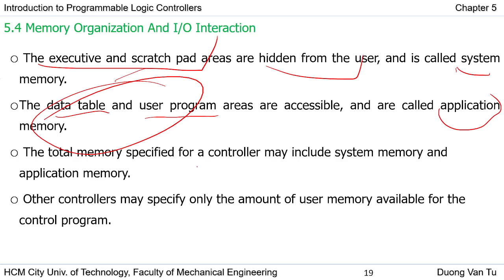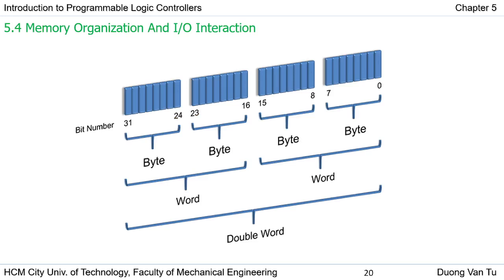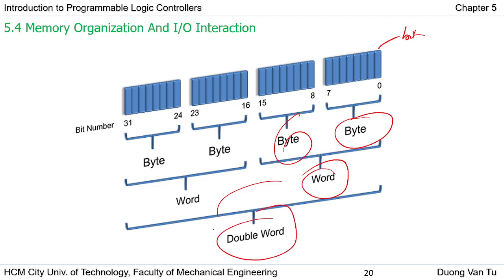The total memory specified for a PLC may include both system memory and application memory, but sometimes only the application memory is considered for control program and data use. To review: the smallest unit in memory is a bit, 8 bits form a byte, 2 bytes form a word, and 2 words form a double word, so one double word contains 32 bits.